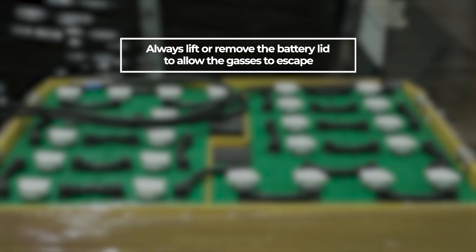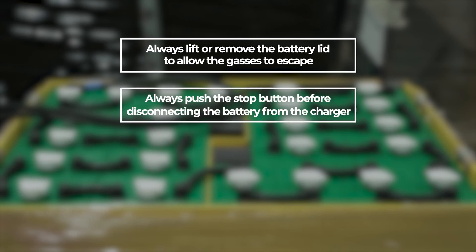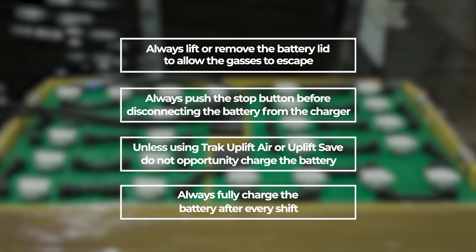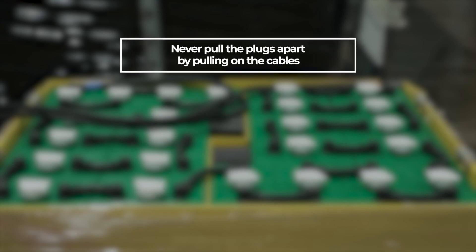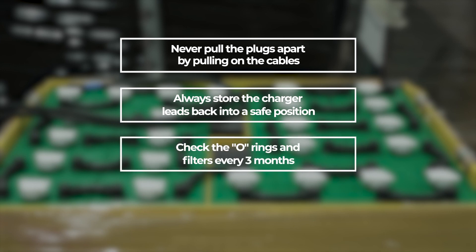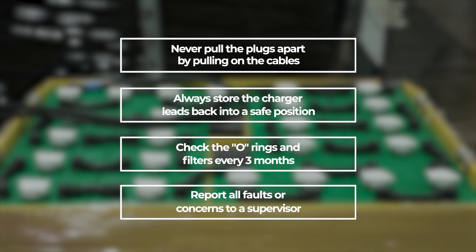Key safety rules: Where possible, always lift or remove the battery lid or reach out to the battery to allow gases to escape. Always push the stop button before disconnecting the battery from the charger. Unless using Trak Uplift Air or Uplift Save, do not opportunity charge the battery. Always fully charge the battery after every shift until a green light, LCD or lamp is indicated. Never pull the plugs apart by pulling on the cables. Always store the charger leads back in a safe position. On HF and track air chargers, check the O-rings and filters every three months. Report all faults, fault codes, damage, malfunction or concerns to a supervisor or manager.